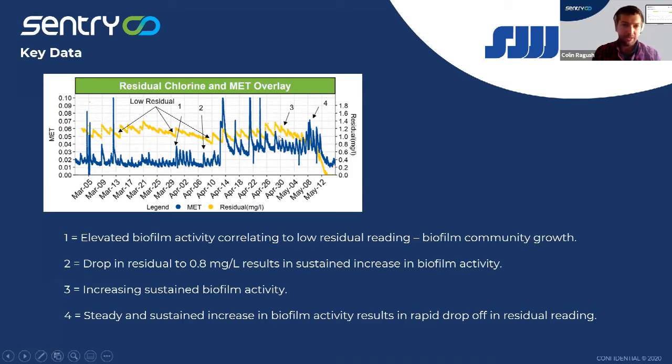This presents a problem for the system, specifically since San Jose is using chloramines. They know that the development of nitrifying conditions is a problem. So we knew we had developed something, and then in early May we started to see a lot of rapid changes in activity, and that's unusual. It tells us that something is devolving or unstable inside this biology. It turns out what that appears to have been is one of these nitrification events. When they get nitrification, they get rapid depletion of the residuals, and sure enough, that's exactly what we saw in this case.